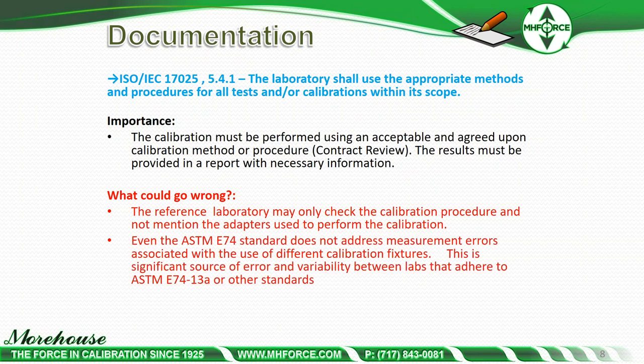Even the ASTM E74 standard does not address measurement errors associated with the use of different calibration fixtures. This is a significant source of error and variability between labs that adhere to ASTM E74-13 or other standards — it's a problem.